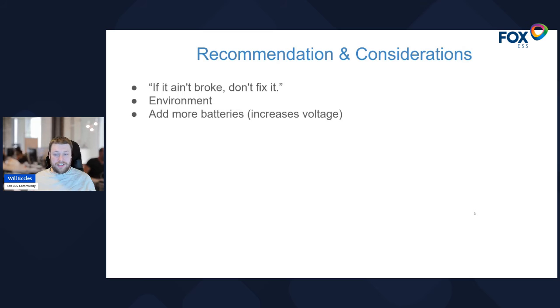You can add more batteries. So if insulating or moving the batteries, or the installation location, isn't going to work, you can increase your voltage by adding more batteries, which gives you more output for the same amps, because output is amps times volts. So if you add a battery or two, you may find you're now above the threshold where the cooler batteries no longer manifest as a problem.